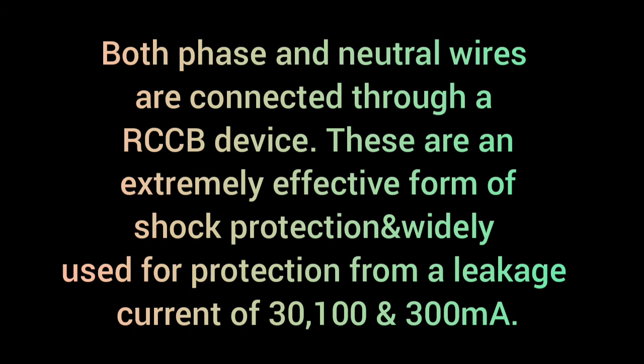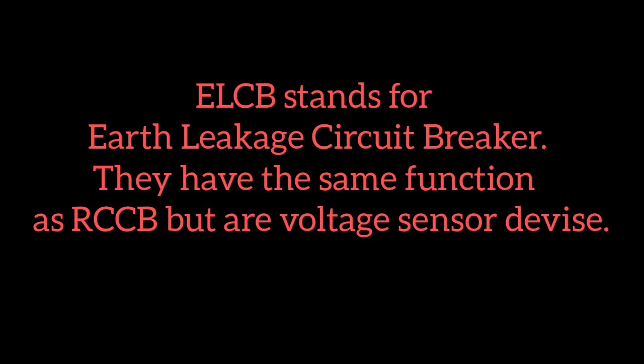Now let's talk about ELCB. ELCB stands for Earth Leakage Circuit Breaker. It has the same function as RCCB but is a voltage sensing device. However, this is an old technology and is not in common use. RCCB, being a current sensitive device, has a better advantage over ELCB. So now let's see what the differences are between ELCB and RCCB.